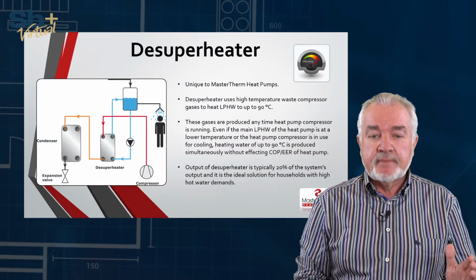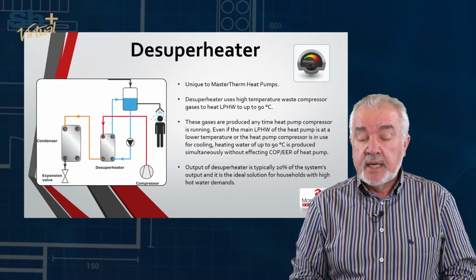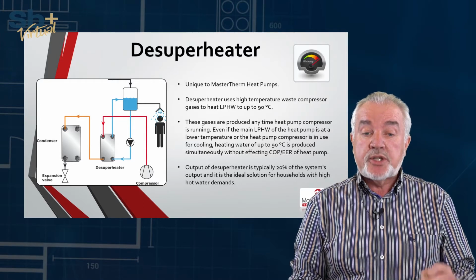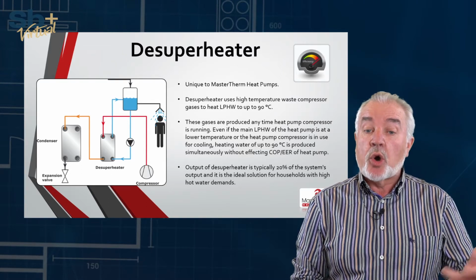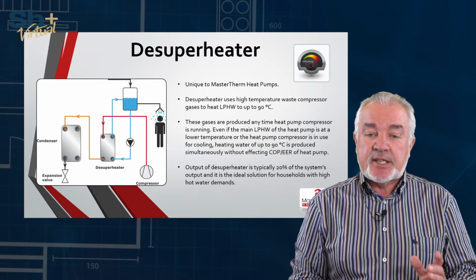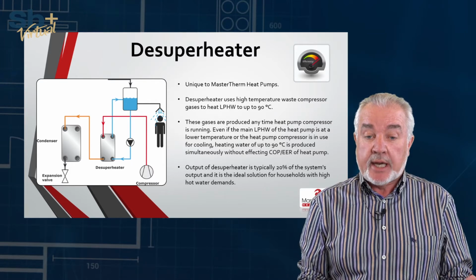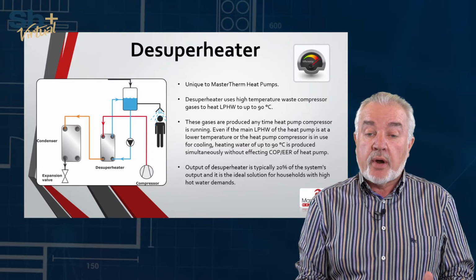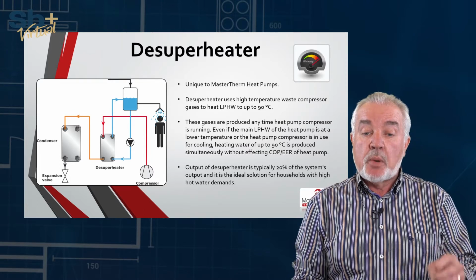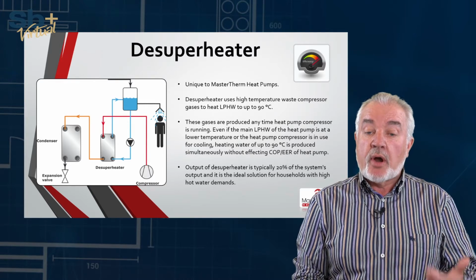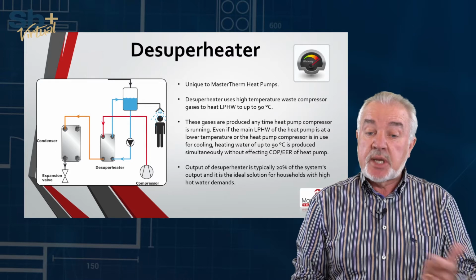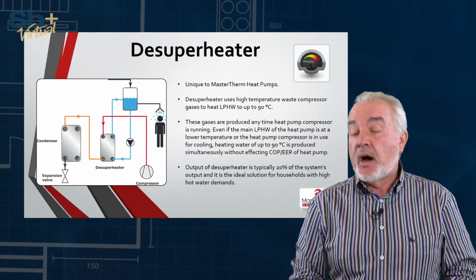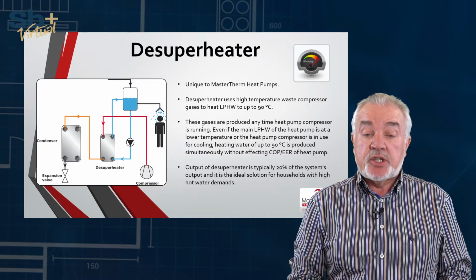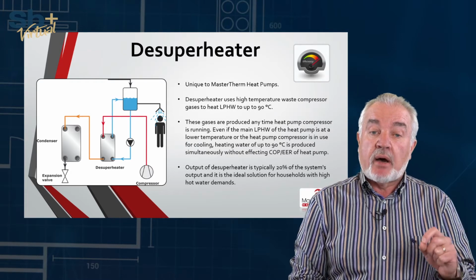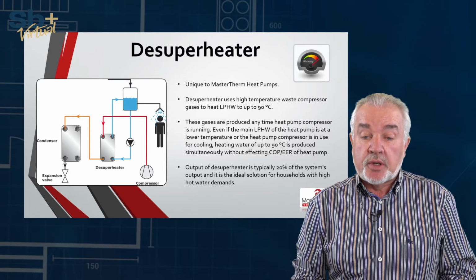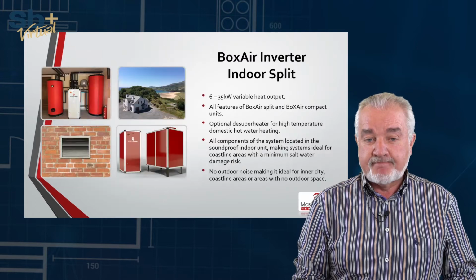What is the de-superheater? Well, it's unique to MasterTherm heat pumps. The de-superheater uses high temperature waste compressor gases to heat the low pressure hot water up to 90 degrees centigrade. These gases are produced anytime a heat pump compressor is running. Even if the main low pressure hot water of the heat pump is at a lower temperature, or the heat pump compressor is in use for cooling, heating water of up to 90 degrees C is produced simultaneously without affecting the efficiency of the heat pump. The output of the de-superheater is typically about 20% of the system's output, and it's the ideal solution for households with high hot water demands.